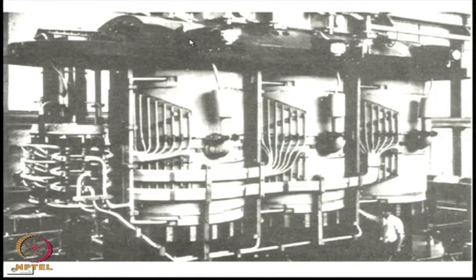Another interesting feature of a 3-phase transformer, which is normally not found on a single phase transformer, is the arrangement of tapping. Tapping is necessary so that the voltage on the HV or LV side can be controlled. The tapping is done by either inserting additional turns in a particular winding or removing some turns from a winding.